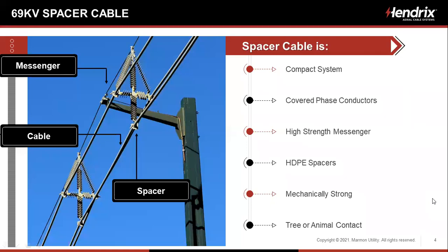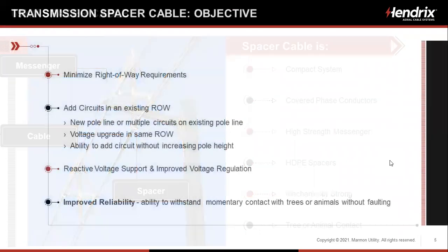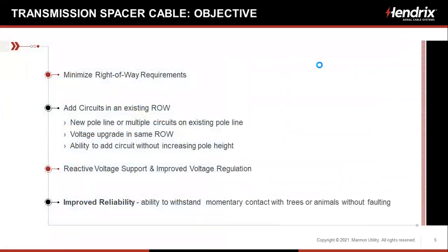So spacer cable is basically a compact system. We've got covered phase conductors. You can see the high strength messenger on top, and we'll describe that a little bit. The spacers are made of high density polyethylene so that they're the same material as the conductor covering, so we don't find ourselves with any dielectric incompatibility issues. The system is mechanically strong and it can withstand tree or animal contact without damage or reliability issues.